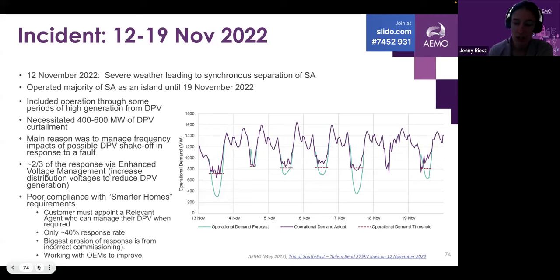The main security risk we were worried about here was while we were operating an island, there is the potential for a fault in the middle of Adelaide that would cause a trip of a unit plus a very large amount of PV disconnecting. And we didn't have adequate frequency reserves to be able to manage that in that island condition and maintain our frequency standards.